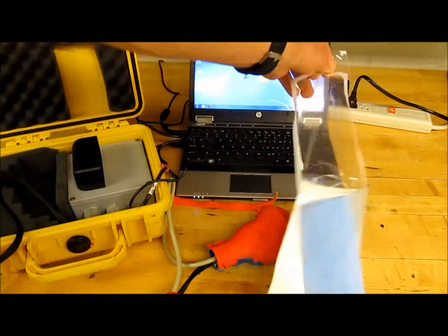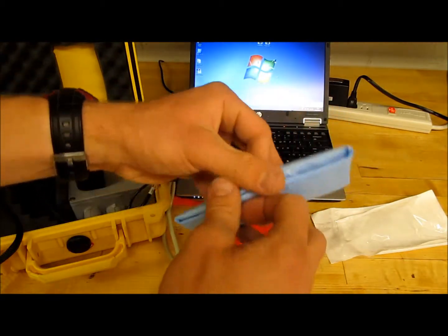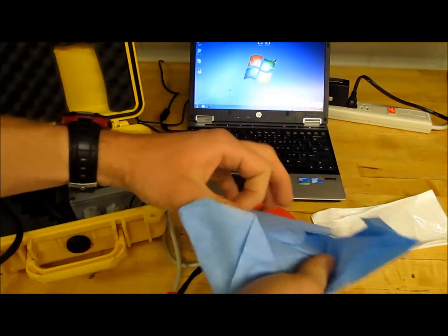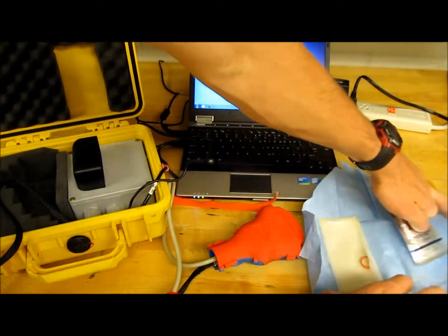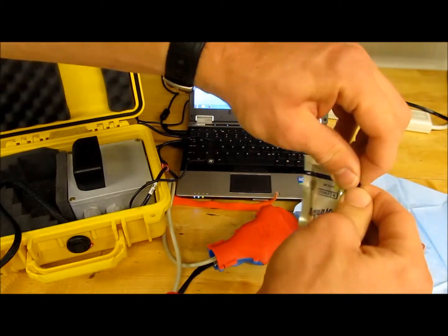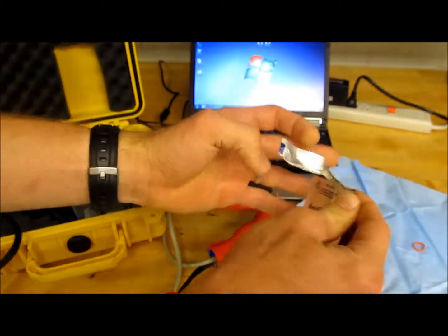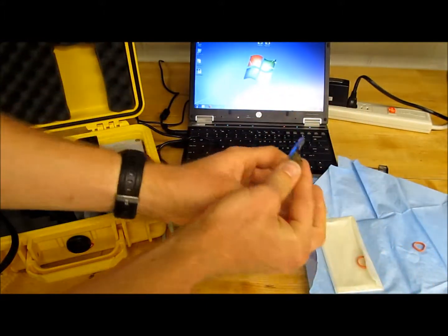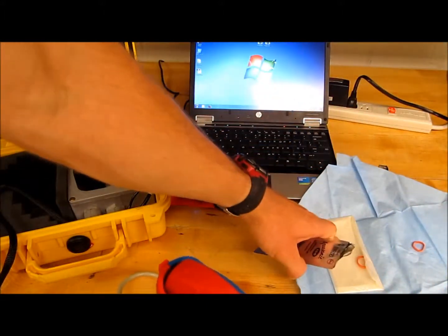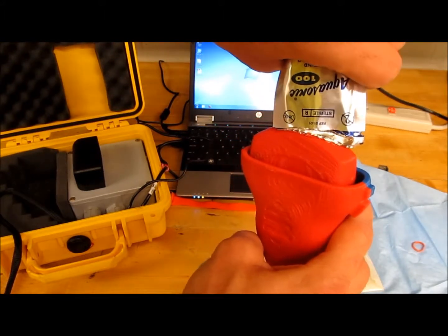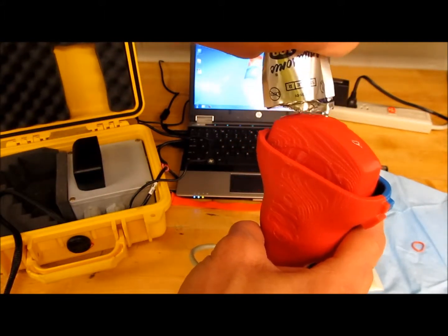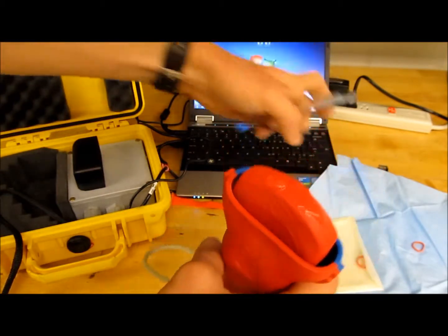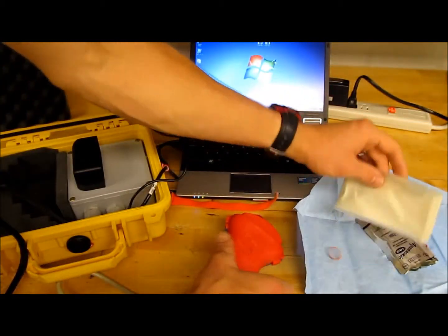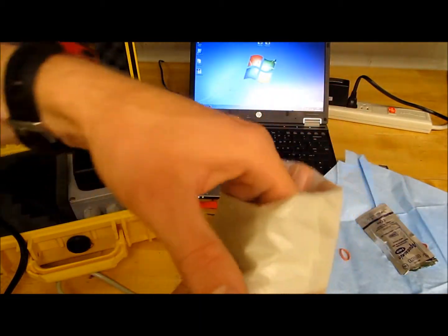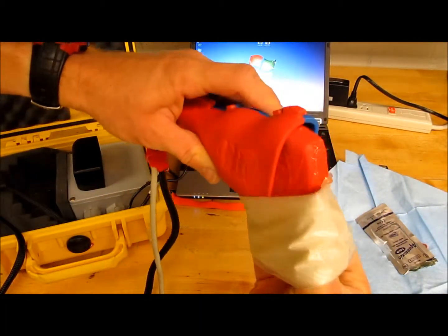So we take our bag. What we first want to do is apply a small amount of gel to the face of the ultrasound transducer. This will help to ensure acoustic coupling between the bag and the transducer itself. So apply a small bit of gel. It's probably good enough. I'm going to put our ultrasound probe into the bag.